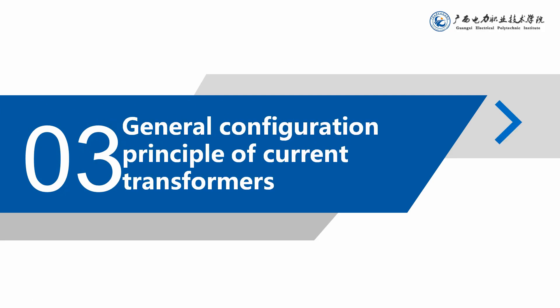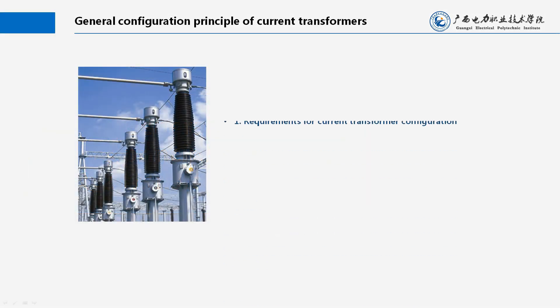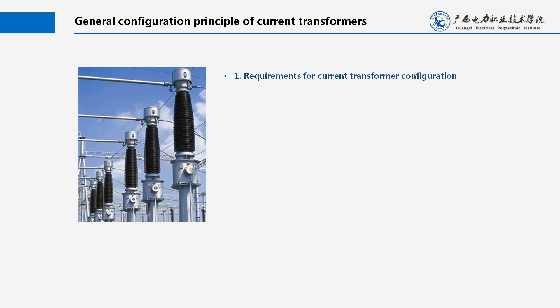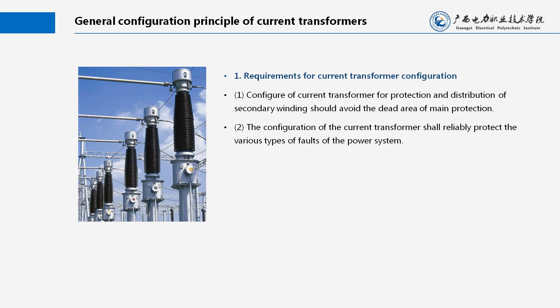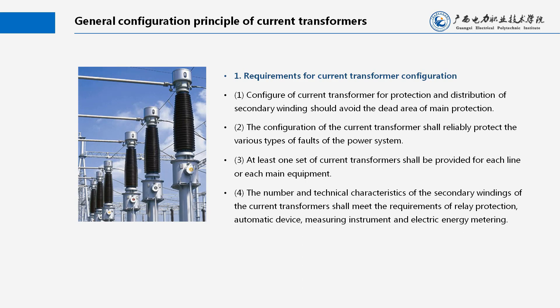General Configuration Principle of Current Transformers. Requirements for Current Transformer Configuration: 1. Configuration of the current transformer for protection and distribution of secondary winding should avoid the dead area of main protection. 2. The configuration shall reliably protect the various types of faults of the power system. 3. At least one set of current transformers shall be provided for each line or each main equipment. 4. The number and technical characteristics of the secondary windings shall meet the requirements of relay protection, automatic device, measuring instrument and electric energy metering.